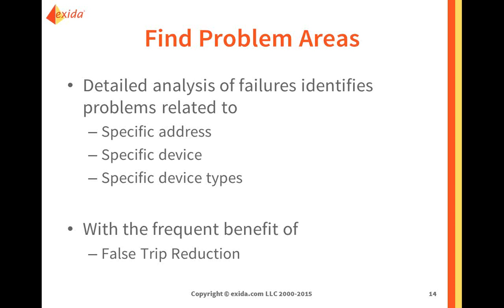And we've talked with many end-user customers, and we've seen with some that at one site, a manufacturer acts as the preferred vendor. At the second site, they're on the blacklist: don't buy from this manufacturer. It's a similar use, but at one site there's just something a little bit different that makes this transmitter not operate the way that everybody is expecting. So it will allow you to identify issues that are specific to a device type, but also to a specific device. So let's say a transmitter failed or a valve failed. Let's say a valve failed, and I take that valve out of service, I send it to a valve body shop, it gets repaired, I get it back, and put it back in service, maybe at a different location.